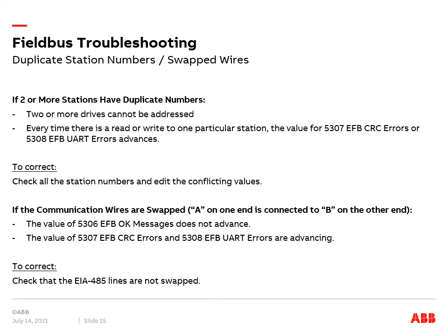To correct duplicate station numbers, check all the station numbers and edit any conflicting values. If communication wires are swapped — in other words, channel A on one end is connected to channel B on the other end — the value of 5306 EFB OK messages does not advance, and the values of 5307 EFB CRC errors and 5308 EFB UART errors will advance. To correct this problem, check that the 485 lines are not swapped.